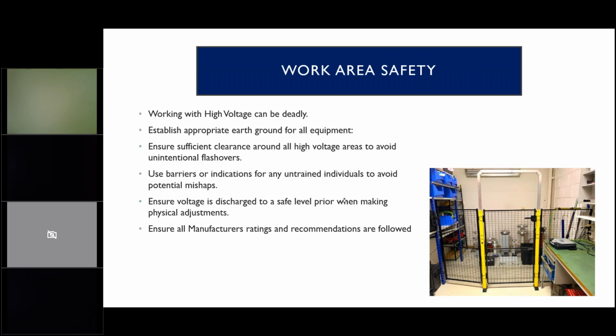When working around high voltage, one of the things you want to do is set up a work area for safety. Obviously, make sure you have good earth grounds, that your power outlet itself has a good earth ground, and that your power cords all have all the wires, and that you've tested those power cords with a HIPOT. You want to ensure there's clearance around anything that's high voltage. And the reason for that is because high voltage can arc over. I used to think that you'd walk by a power line, and if you didn't get near it, you'd be safe. That's before I realized that, through capacitive coupling, it can arc over even if you're 3 or 4 feet away and can get you.